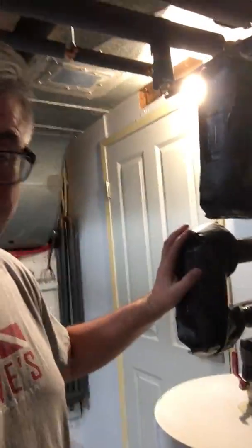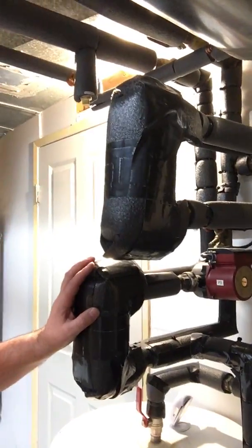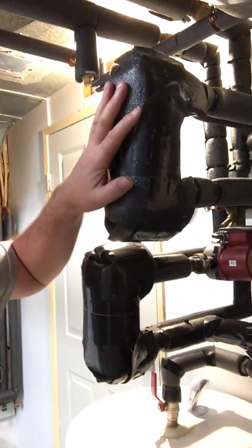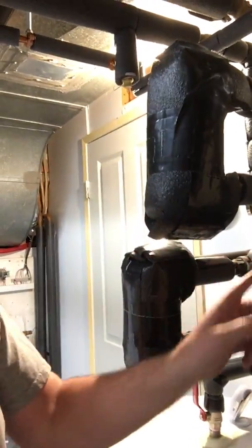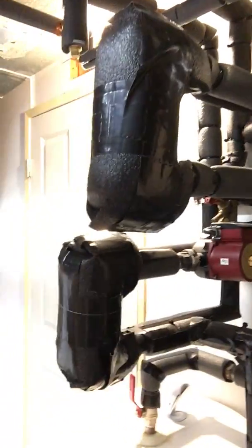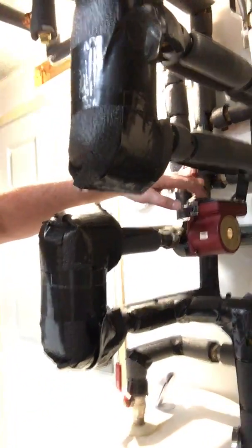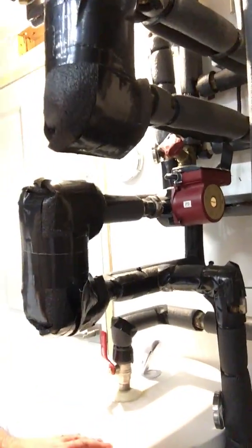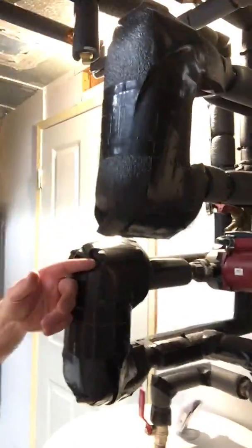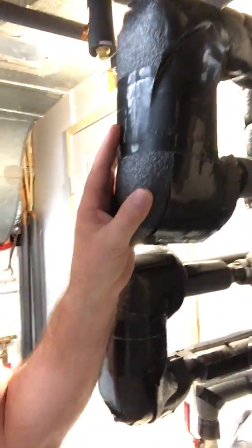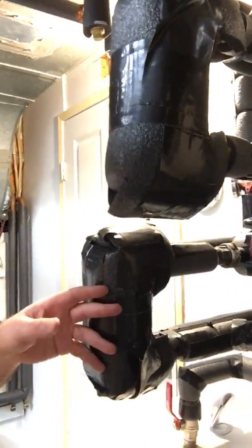All right, now, this is our domestic water system. So we have a preheat and a reheat. All the water coming from the city first goes through this heat exchanger on the domestic side, then goes into the tank at the back. And then we have this circulator, and that circulator pulls the water from the tank and reheats the water. So the water comes through the preheater and then goes into the tank, and then it's reheated through this exchanger here.